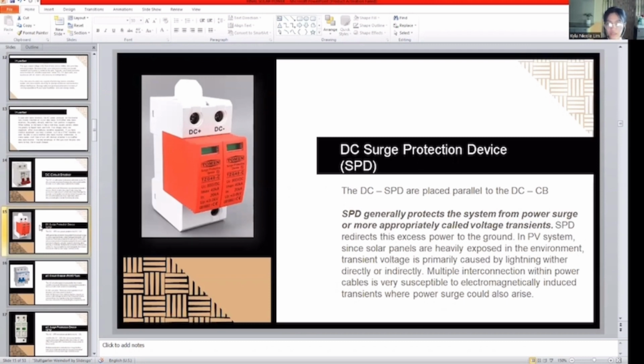The next one is the DC surge protection device, or SPD. The DC SPD is placed parallel to the DC CB. SPD generally protects the system from power surge, or more appropriately called voltage transients. SPD redirects this excess power to the ground. In PV systems, since solar panels are heavily exposed to the environment, transient voltage is primarily caused by lightning, whether directly or indirectly.